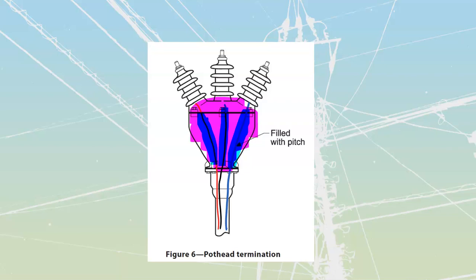We can use these on other types of cables, but it's less commonly used on other types. The other thing is, if you run into these in the field and get asked to take them apart, be aware that a lot of the time the pitch or tar inside was treated with, wait for it, PCBs — because we have something that burns, pitch or tar, but we don't want it to burn, so we add some chemicals to the inside of it.